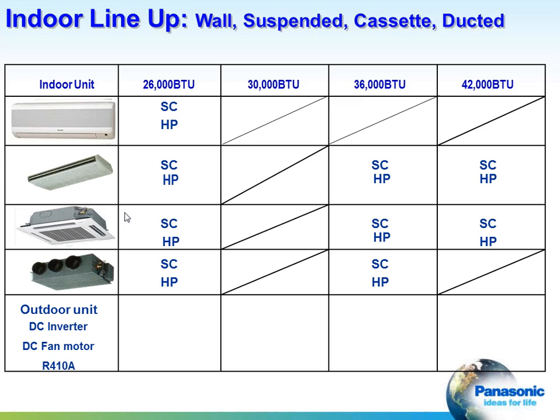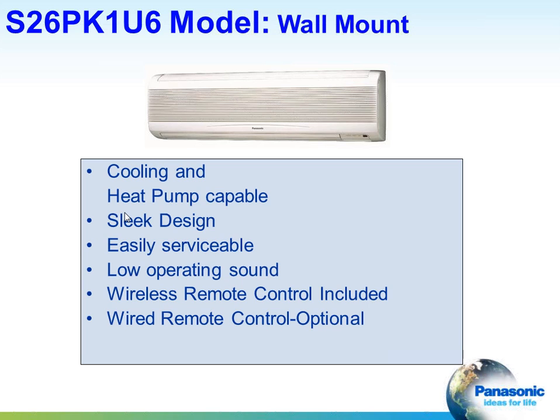Here's the greater variety of indoor units that are available on the Pac product. We have the high wall unit, the ceiling suspended, ceiling cassette, and a ductable unit. This is the high wall unit. It's cooling and heat pump capable, so it comes in both cooling only and heat pump. Nice design, easily serviced. It's a relatively small unit. The front cover opens for access to wiring and other controls and other parts. Very quiet. Typically, there's going to be other devices in the room that will be louder than this unit here.